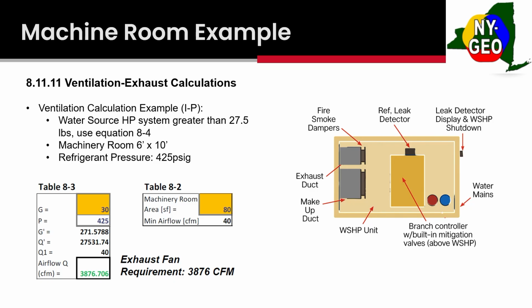ASHRAE 15 has ventilation requirements under Section 8. So I just did an example of a small heat pump here. It's got 27.5 pounds, that would be a 40 to 50 ton heat pump. We've got a small machine room here, 6 by 10, and our refrigerant pressure is 425. I'm not going to go through the formula. I don't want to bore everyone to death by going through formulas.